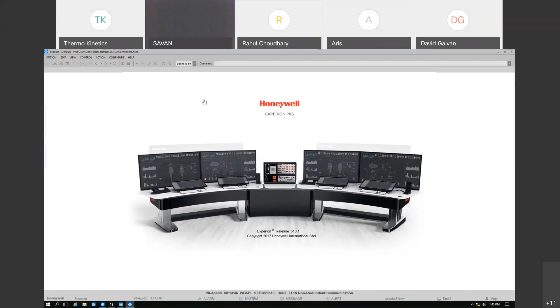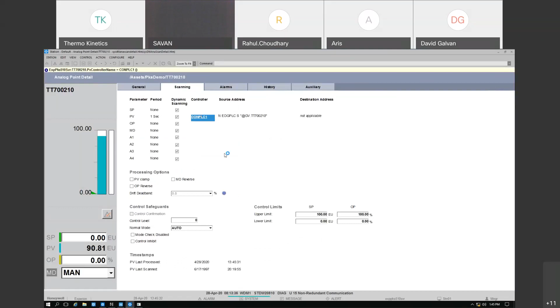If I double click, so this is the temperature transmitter that I have off of the PLC. Okay, let's go to scanning. Let's go to COM PLC1. So here's the PLC. When I hit that publish to Experion, it gave me all these points automatically. It did all of this tagging for me. I didn't have to do any of that. It did it with a one shot. It brought diagnostics. It brought my instrumentation.